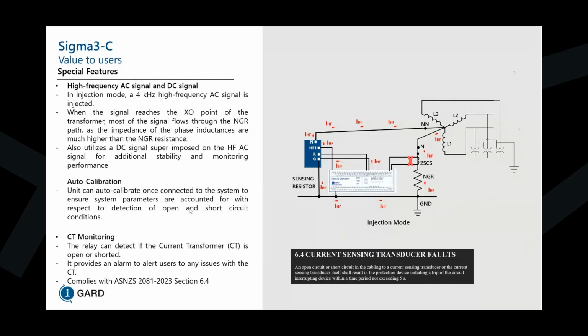This came about because there was quite a considerable amount of installations that were experiencing CT damage, and that CT damage didn't allow for the resistor monitoring to properly work and potentially cause nuisance alarms. So this capability for this relay allows it to provide the operator additional benefit in understanding that the CT itself has failed, rather than going through all the troubleshooting process to find that out later.